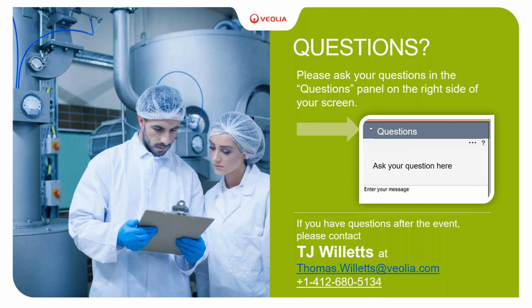Okay, another question that came in for the header checks: what percentage of flow loss necessitates some remediation efforts? I say 10% difference. Do you agree with that, Jack? Yeah. So if your normal flow through a header is 1,000 gallons per minute, if you get down below 900, then yeah, something's probably not right. You probably got a clog somewhere in that line. If it's clogged, it's pretty evident. You know, the flow changes quite a bit.